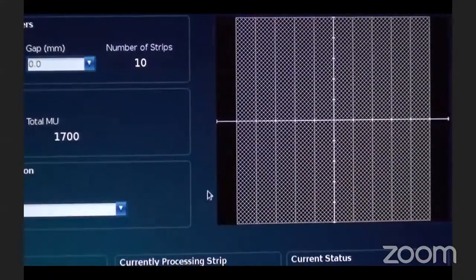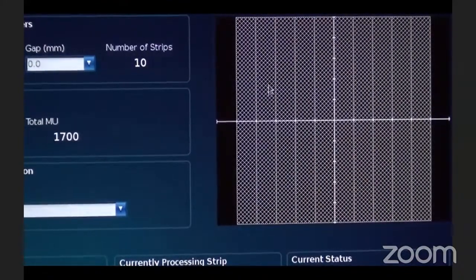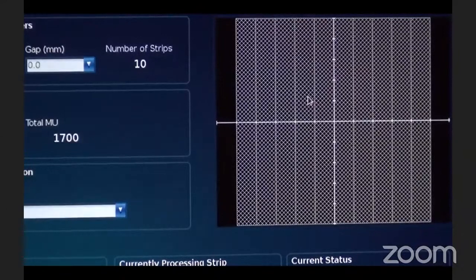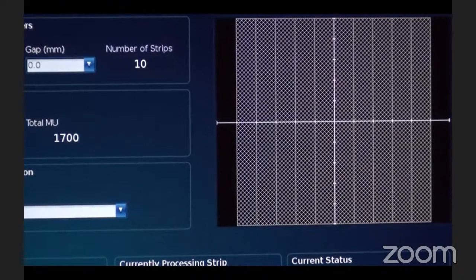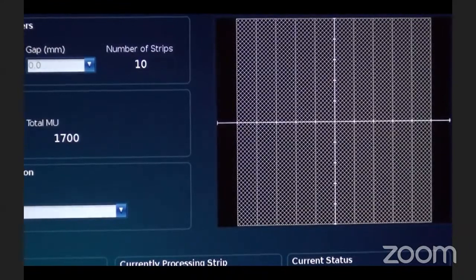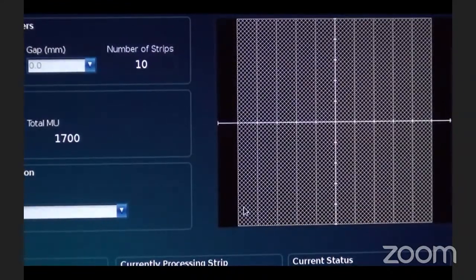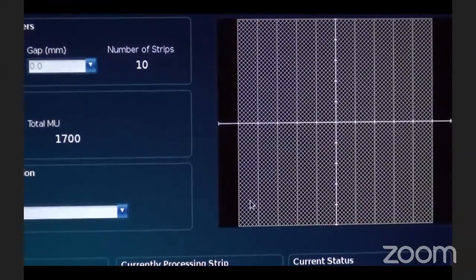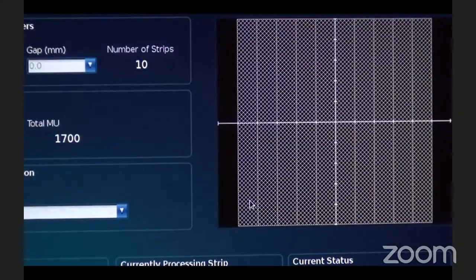For the picket fence test, we deliver 10 fields connected to each other. Each of the fields has a width of 10 mm. For each field, we deliver 170 monitor units on the GafChromic film attached to the edge of the top of the multi-leaf collimator. This is how the first beam is delivered, and then the fields are delivered one by one.